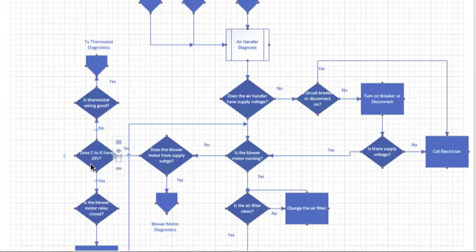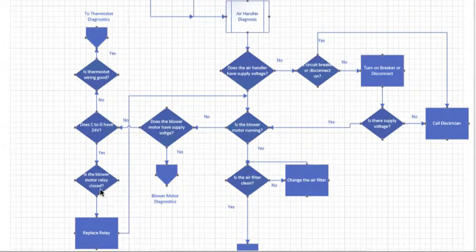So again, if you don't have it, check the thermostat wiring. If the thermostat wiring is good, you've got to go back to your thermostat diagnostics because you missed something on the thermostat. If the thermostat wiring is not good, you have to correct that before you can go any further. If I have 24 volts between C and G, you need to check and see if the blower motor relay is closed. Now, this is assuming there's still a relay. If there's a circuit board, you're going to have a bad circuit board at this point. If the blower motor relay is closed and you're not getting power to your blower motor, you have a faulty relay. Replace the relay. Real easy, but then you're going to come back and start the process over again.